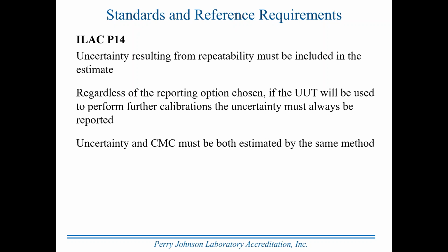All right, uncertainty and CMC must both be estimated by the same method. It's important for us to talk a little bit about CMC. This stands for calibration and measurement capability. This used to be referred to as best measurement capability, BMC. And what it says in ILAC P14 is that when you're estimating the uncertainty of measurement for a calibration you performed, or when you're estimating the calibration and measurement capability of your laboratory, those estimates must both be done by the same method. CMC is the hypothetical state of the uncertainty that occurs when you're calibrating the very best piece of equipment under ideal conditions. So if you're estimating uncertainty, you're going to be maybe close to ideal conditions, but not quite.